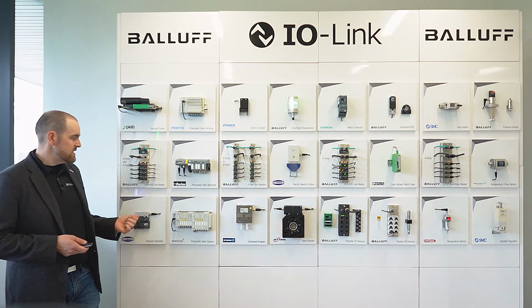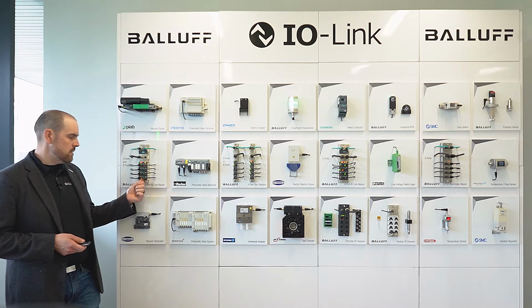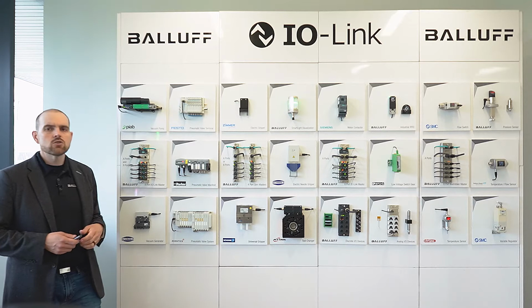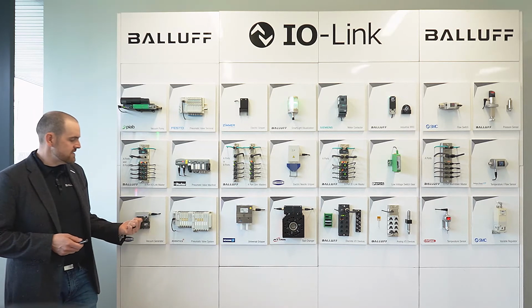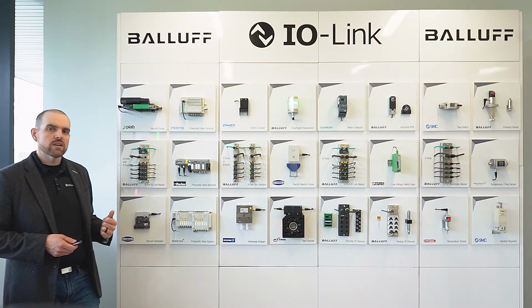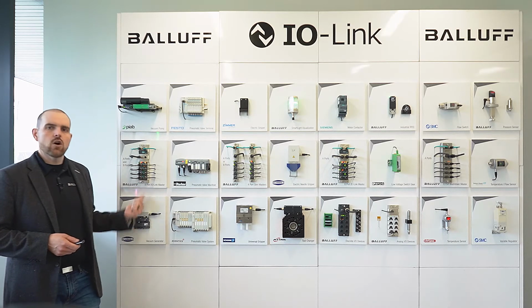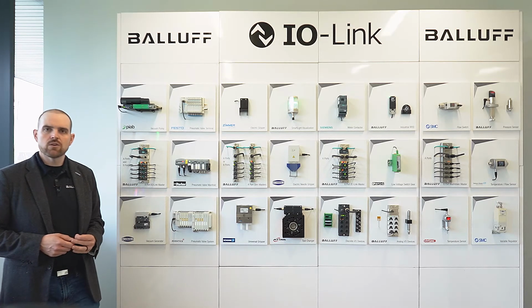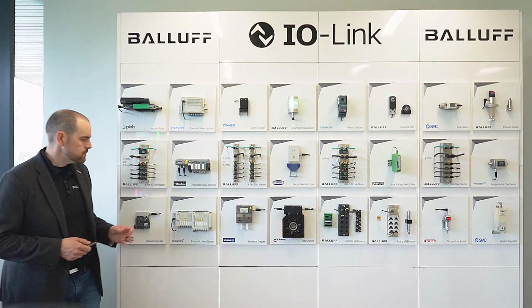What's nice is with a master, like the master from Balluff, you can actually suck the parameters and the settings out of this device. You can store them in the master, so if this device gets damaged or fails, you can swap it out and the master automatically tells it what its previous configuration was, which is really slick.